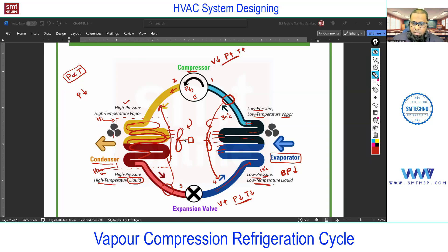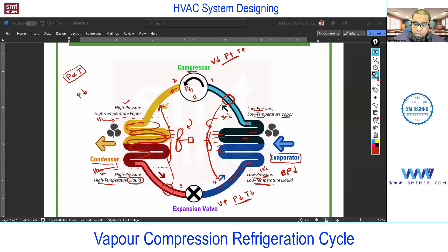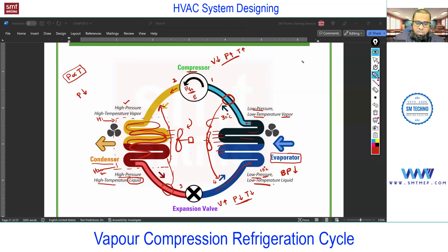The same case on the high side also — temperature and pressure will be the same but phase change occurs in the condensing coil. To clarify the components: after the condenser you'll find the receiver; after the evaporator you'll find the accumulator. The receiver after the condenser will not allow any gas into the expansion device; the accumulator will not allow any liquid into the compressor because it's a vapor compressor — the compressor is designed to compress refrigerant in the gas state.